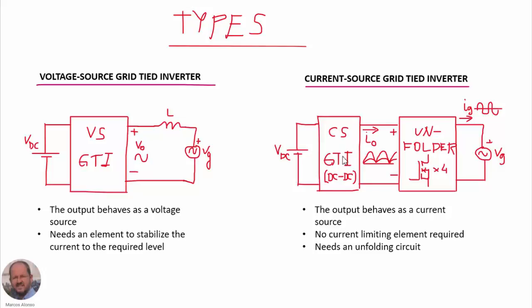The other type is the current source grid-tied inverter. In this case, the inverter behaves like a current source at the output, so we can modulate the current to have a sinusoidal waveform and inject it into the grid. The inverter is in reality a DC-DC converter in which we modulate a control parameter to obtain the correct sinusoidal waveform. We need an unfolding circuit, usually a full bridge made with four transistors, to inject a sinusoidal current into the grid. In this case, we don't need a current-limiting element, but we do need the unfolding circuit.